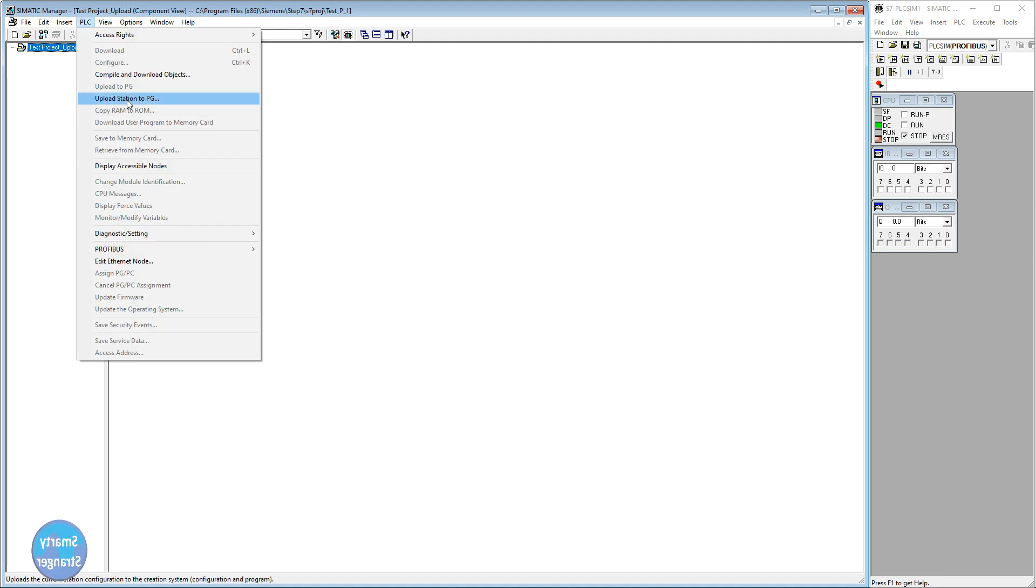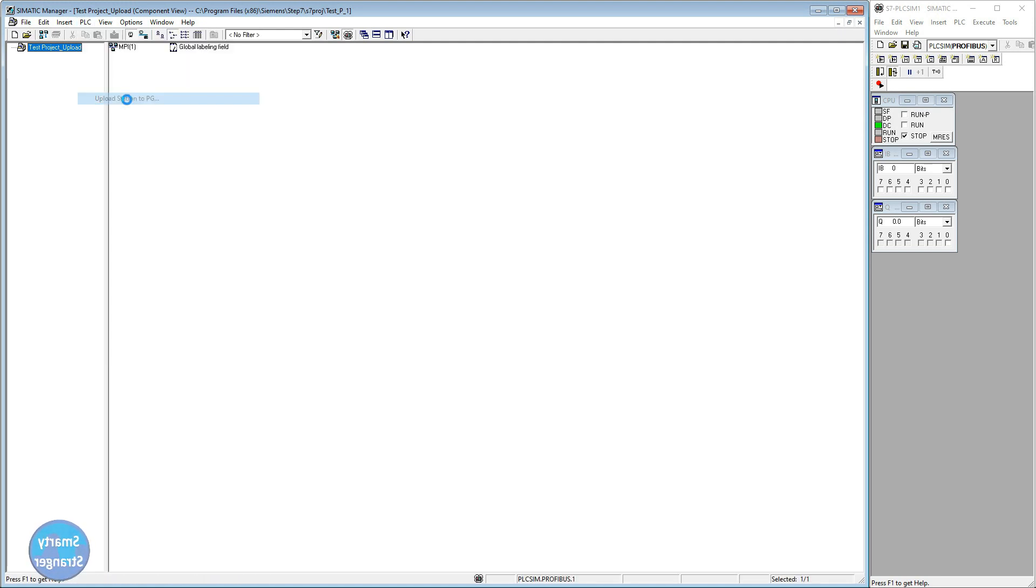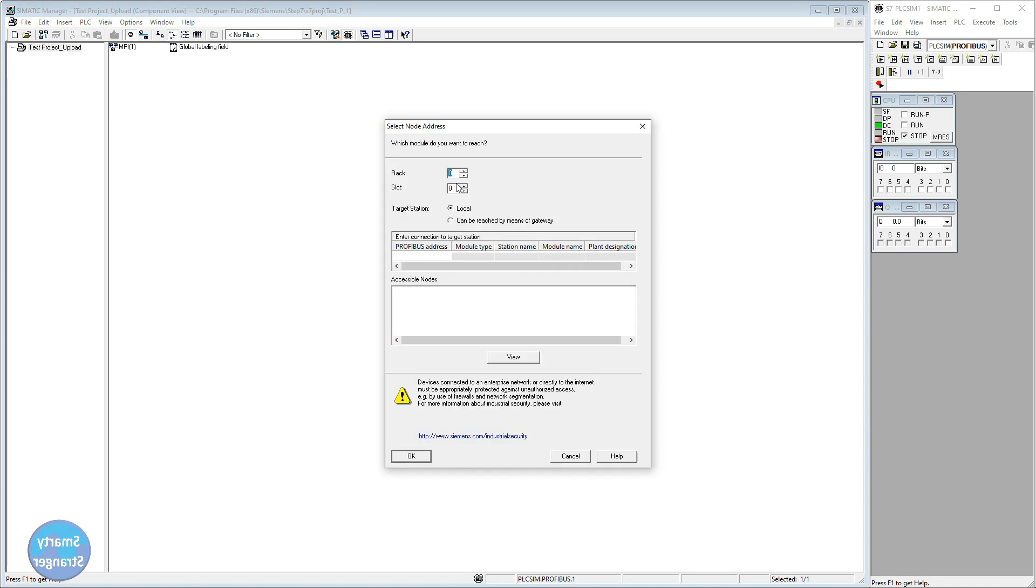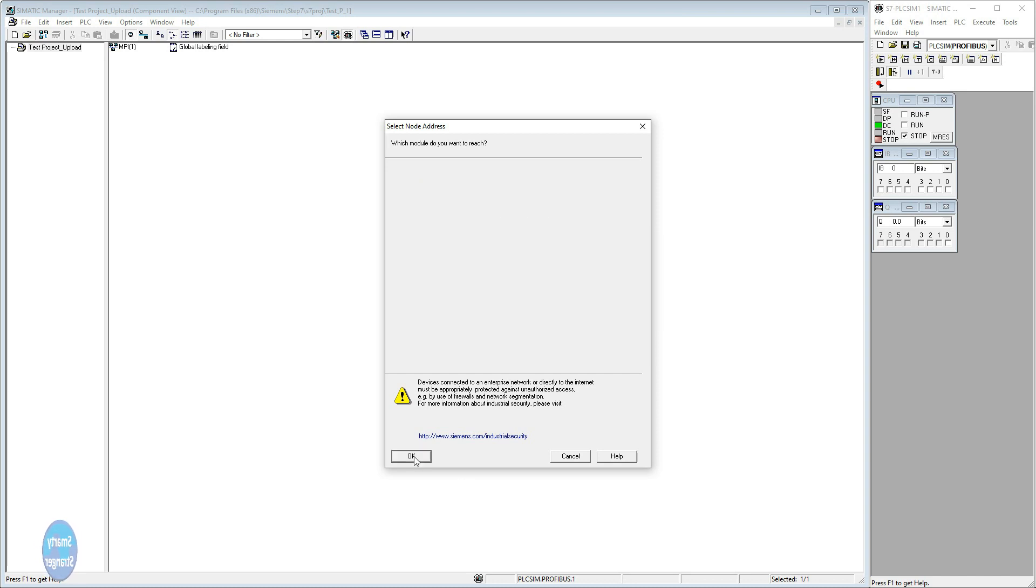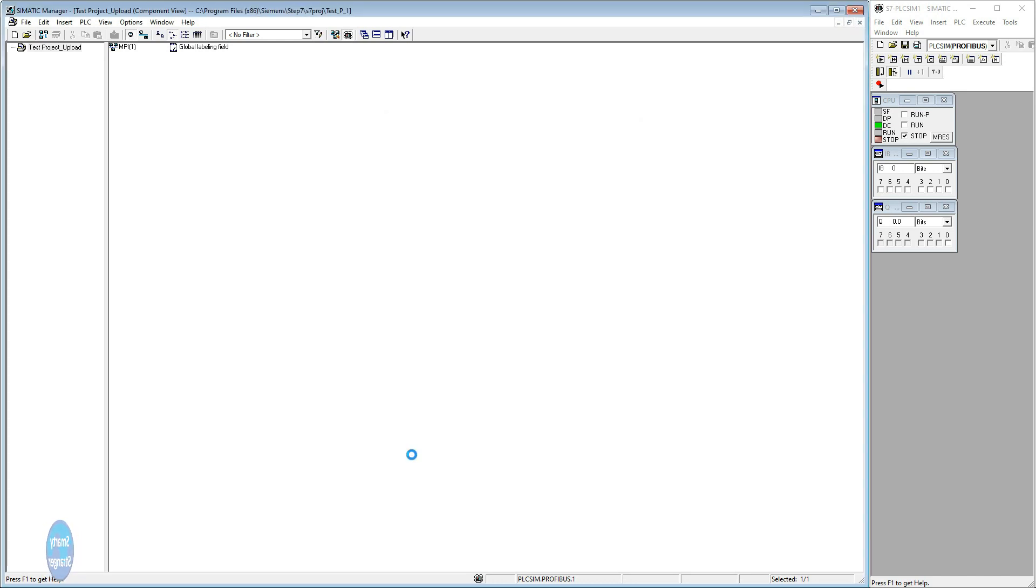Go to PLC tab, click on upload station to PG. A new pop-up will open. Select rack 0 and slot address 2 because CPU is placed on slot 2. Click on view button. When accessible nodes appear, click on your CPU and then click OK button.